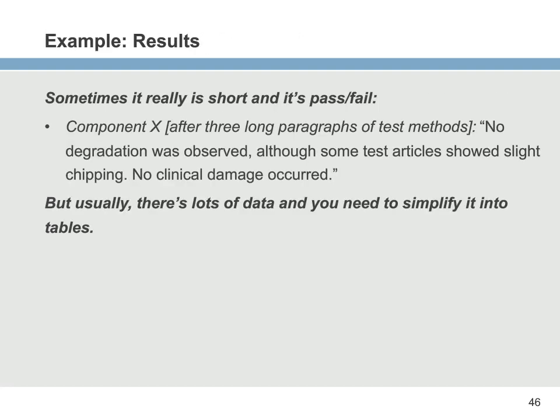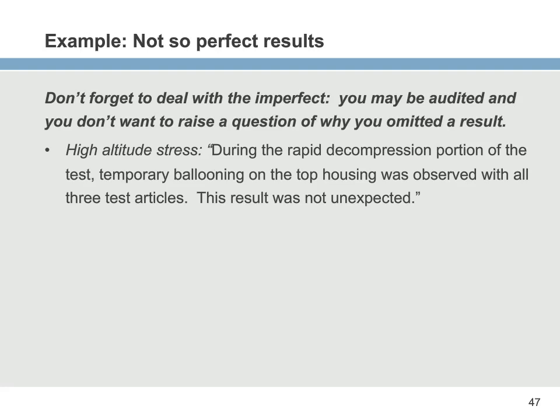Results - sometimes it really is short and pass-fail, which is what we always hope for. After describing three paragraphs of method, it's easy to say there was no degradation observed, although some test articles showed slight chipping and no clinical damage. That's really great. But a lot of times the results aren't so perfect, and it's really important that you deal with it - that's probably the 5th or 6th time we've said that, and it's worth saying.